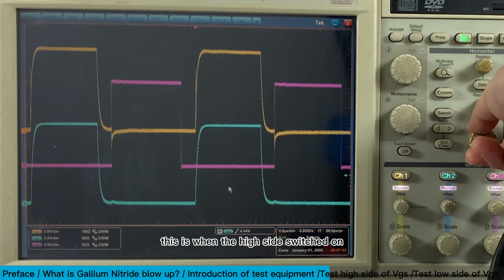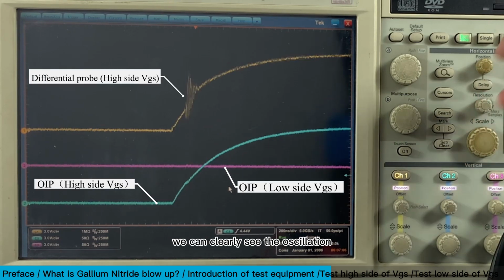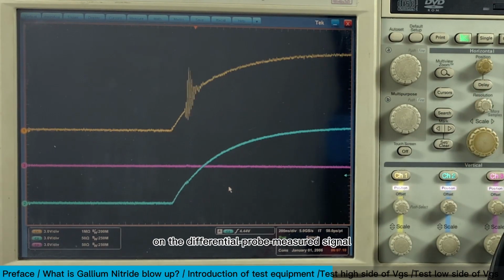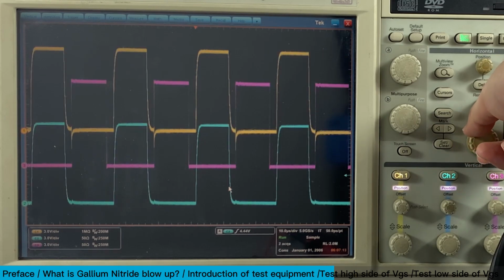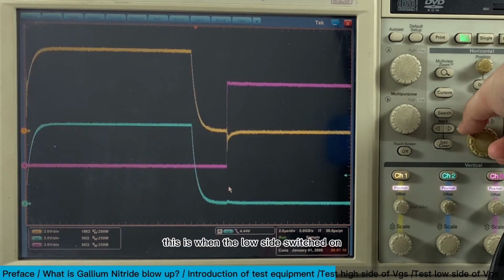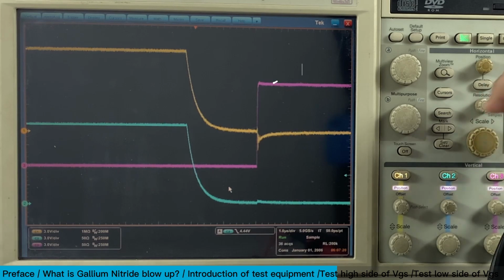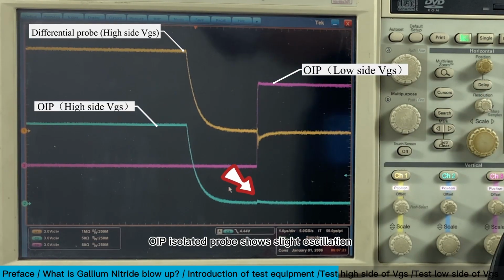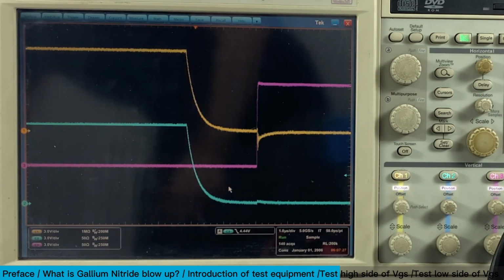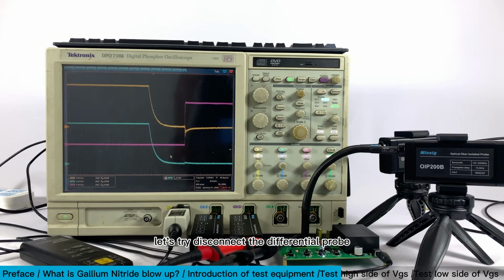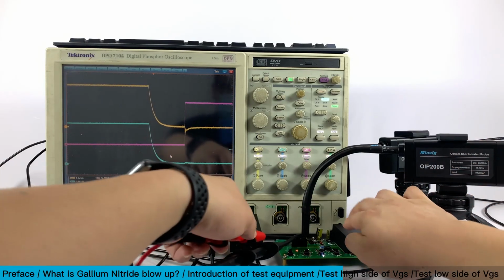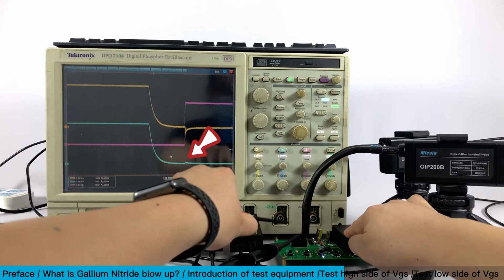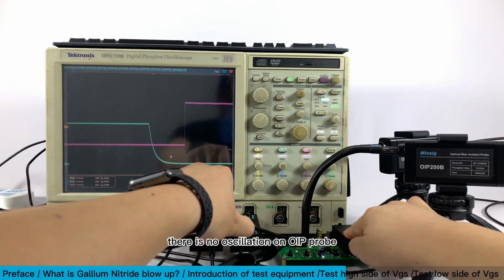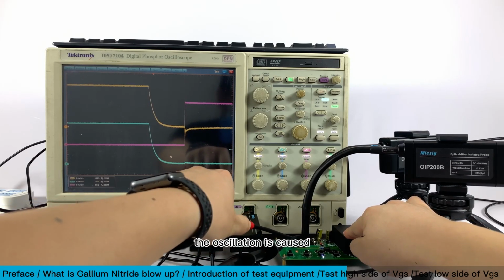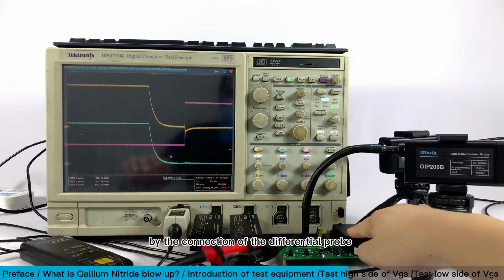This is when the high side is switched on. We can clearly see the oscillation on the signal measured by the differential probe. This is when the low side is switched on. The OIP isolated probe shows slight oscillation. Let's try disconnecting the differential probe. There is no oscillation on the OIP probe. It shows that the oscillation is caused by the connection of the differential probe.